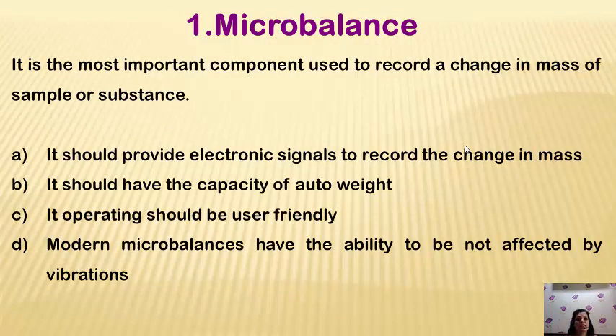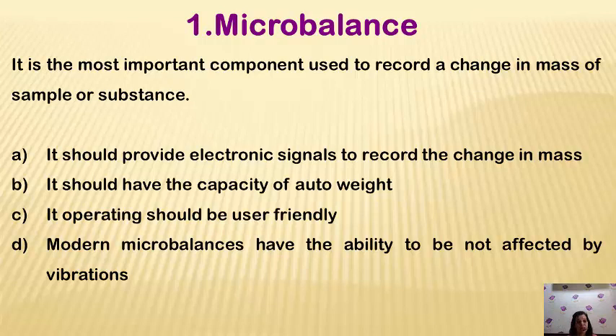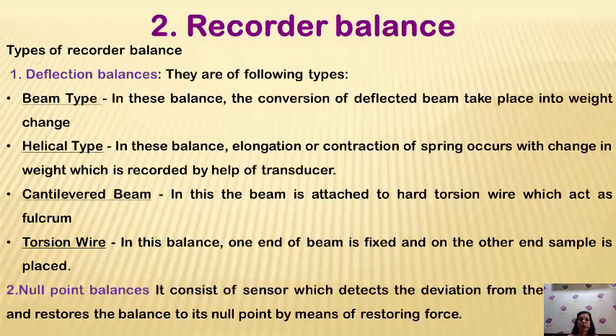The micro-balance is the most important unit of thermo-gravimetric analysis. You are taking a definite amount of sample and recording the change in mass. It provides an electronic signal with change in mass. It should have a capacity for auto-weight and should operate user-friendly. Modern micro-balances are not affected by vibrations. The recorder balance records and shows the change in weight with respect to deflection. There are two types: deflection balance and null point balance.